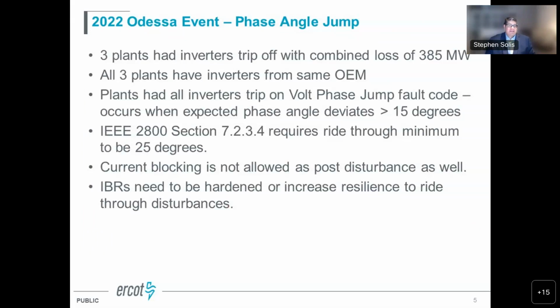And so we had 3 plants that lost 385 megawatts due to phase angle jump trips, all with the same OEM. The plants had all inverters trip with expected phase angle deviation greater than 15 degrees. So that's where it was set. Now, if you compare IEEE 2800, section 7234 identifies a minimum of 25 degrees. So that would have given us some additional bandwidth to potentially prevent some of those trips. So if we would have had the settings set to be compliant with IEEE 2800, we may have avoided some of the lost megawatts during that trip.